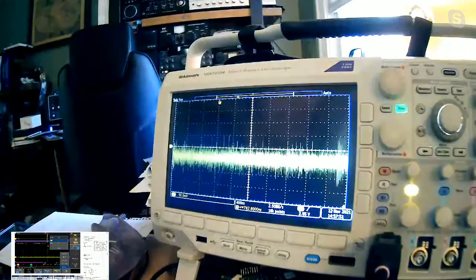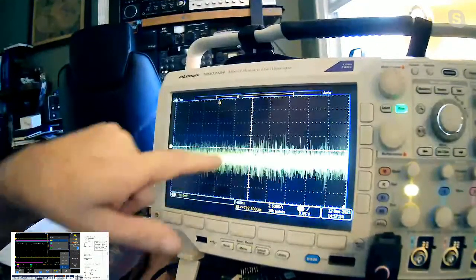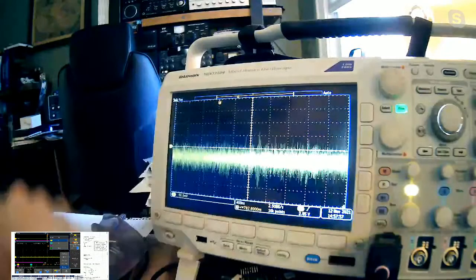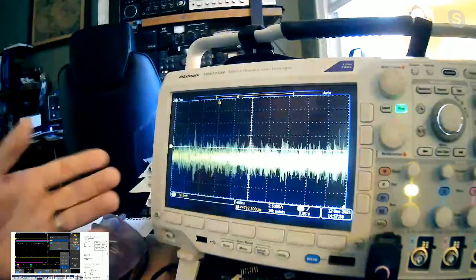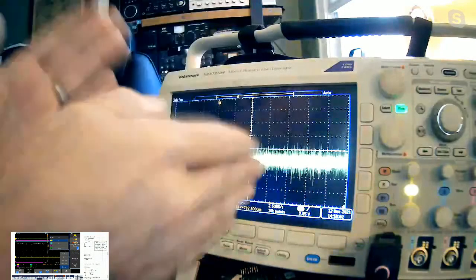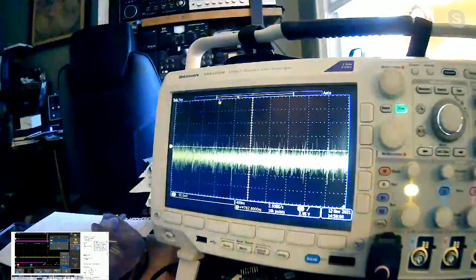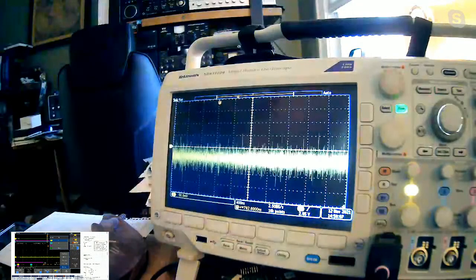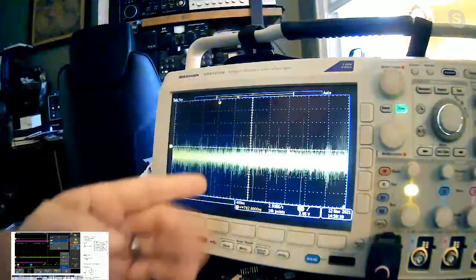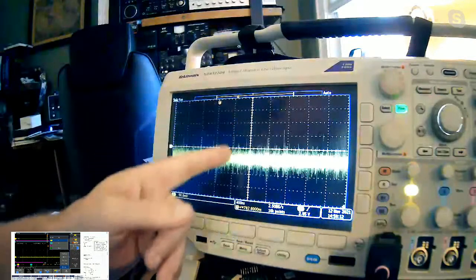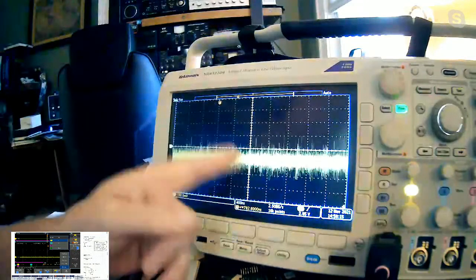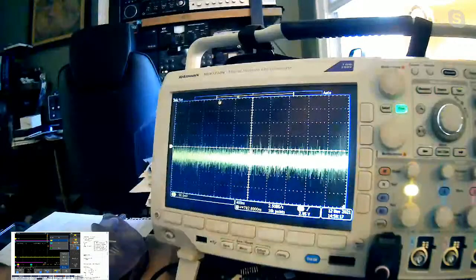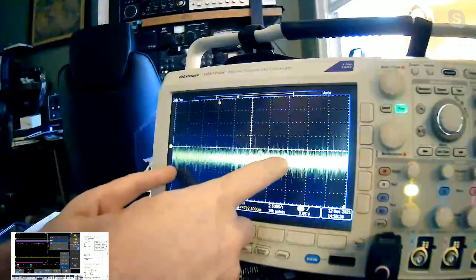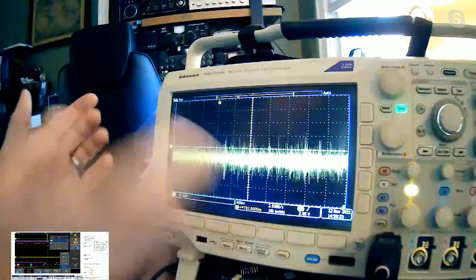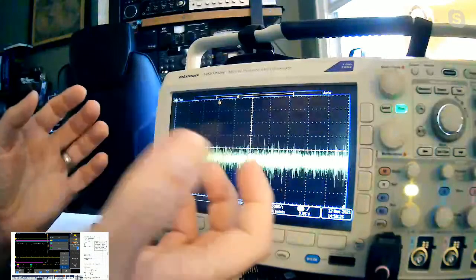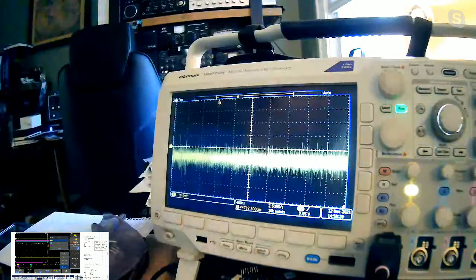What it's doing oftentimes is making the measurements on the displayed points, not the actual waveform record. So if you captured a 10 million point record that has a bunch of really fast edges on it, and I tell a Tekscope to make a rise time measurement, it'll actually measure it, even though that rise time might only occupy a pixel on this display. It'll measure it properly because it's using the waveform record. Some scopes use the displayed points and won't be able to give you that measurement, or they'll give you an incorrect measurement because it's made on a decimated set of samples. Software people.